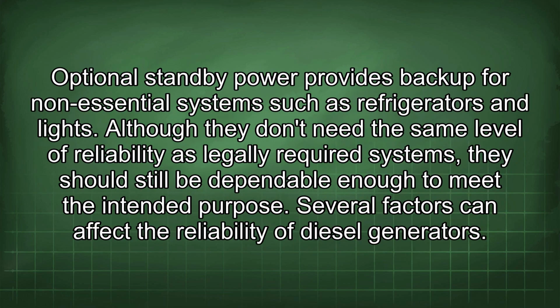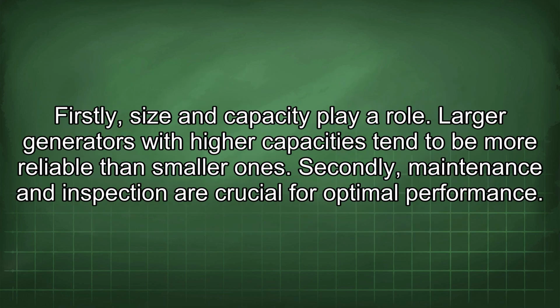Optional standby power provides backup for non-essential systems such as refrigerators and lights. Although they don't need the same level of reliability as legally required systems, they should still be dependable enough to meet the intended purpose. Several factors can affect the reliability of diesel generators. Firstly, size and capacity play a role. Larger generators with higher capacities tend to be more reliable than smaller ones.